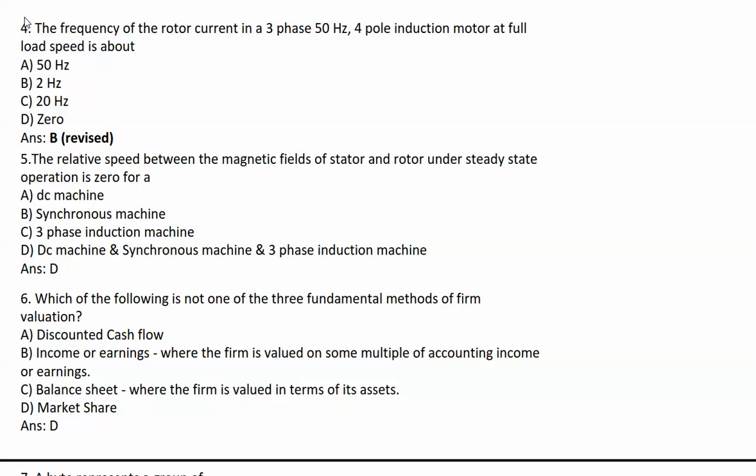Next question: The frequency of the rotor current in a 3-phase 50Hz 4-pole induction motor at full load speed is about. We need to calculate full load speed. First, Ns = 120f/P, so 120 times 50 divided by 4 equals 1500 rpm.